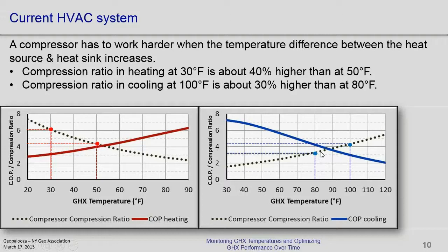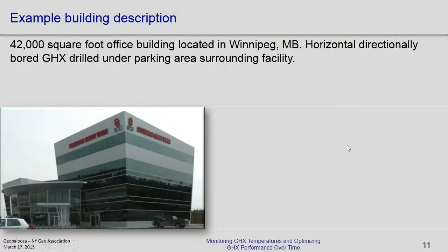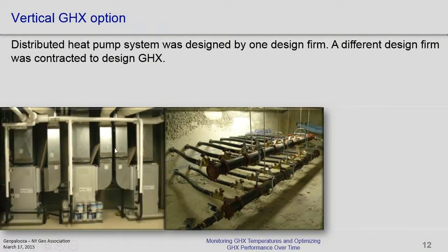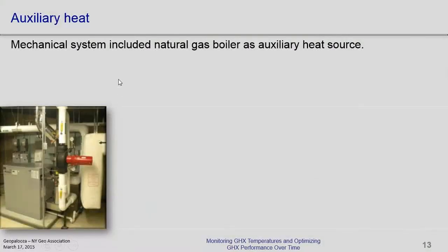As one example of a building, this is located in Winnipeg, about 42,000 square feet, with horizontal directionally drilled boreholes under the parking lot area and a distributed heat pump system throughout the building. What happened on this particular building was that one mechanical engineering firm designed the distribution system and the heat pump system, and then another firm designed the ground heat exchanger based on the loads. No one person was really completely in charge of that system. And then the system was designed with a gas boiler as an auxiliary heat source.